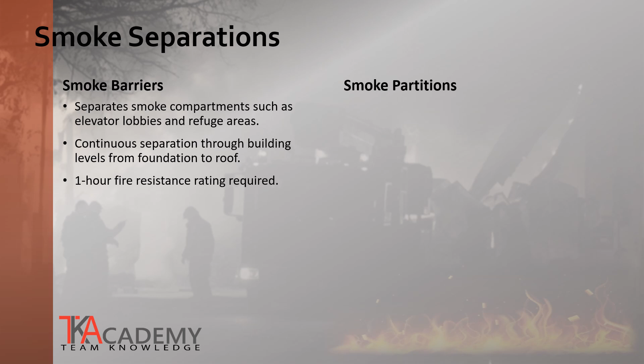Similarly, a building can have smoke separations that are meant to compartmentalize smoke and keep it from being transmitted throughout a building. There are smoke barriers and smoke partitions. A smoke barrier separates smoke compartments, such as an elevator lobby and refuge areas. It is a continuous separation through the building levels from foundation to roof and will have a 1 hour fire resistance rating. Note that a smoke barrier is a 1 hour fire resistant barrier, but a 1 hour fire resistant barrier is not a smoke barrier.